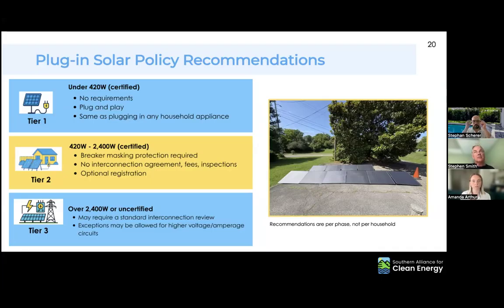We do think it's important that you're in touch with your local utility company, demonstrating that you've thought it through. Above 2.4 kW, or 2,400 watts, we think that may require more of an interconnect agreement, since you're getting higher power output and more amperage, and these things need to be thought through a bit more. So at that level, you probably need to be working with your utility in more ways than just plugging it in without identifying it.